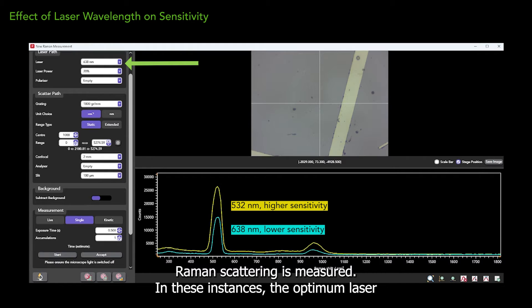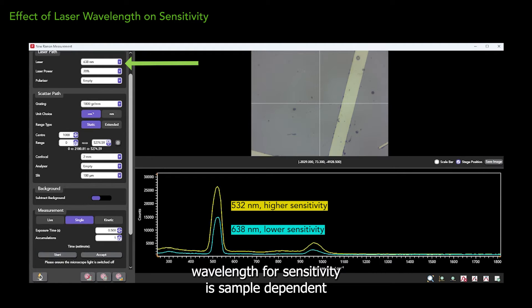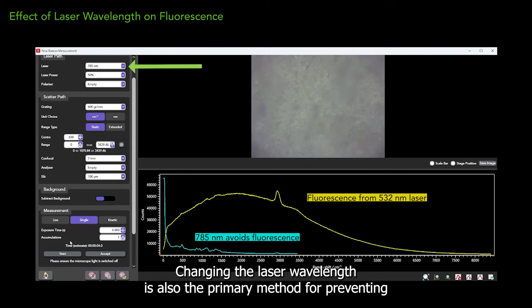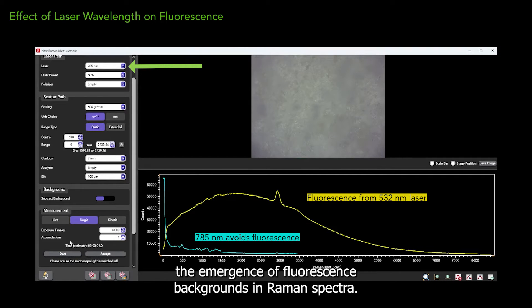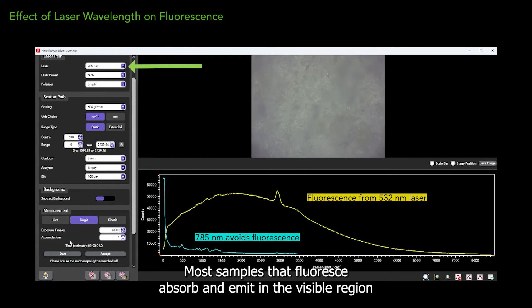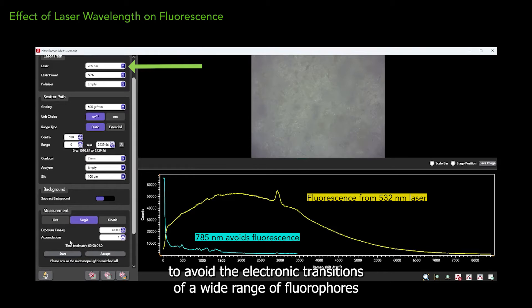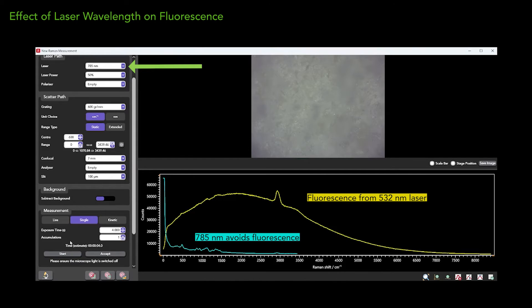In these instances, the optimum laser wavelength for sensitivity is sample dependent. Changing the laser wavelength is also the primary method for preventing the emergence of fluorescence backgrounds in Raman spectra. Most samples that fluoresce absorb and emit in the visible region. Therefore, lasers in the near-infrared, and even in the UV, can be used to avoid the electronic transitions of a wide range of fluorophores. This is also heavily sample dependent, however.